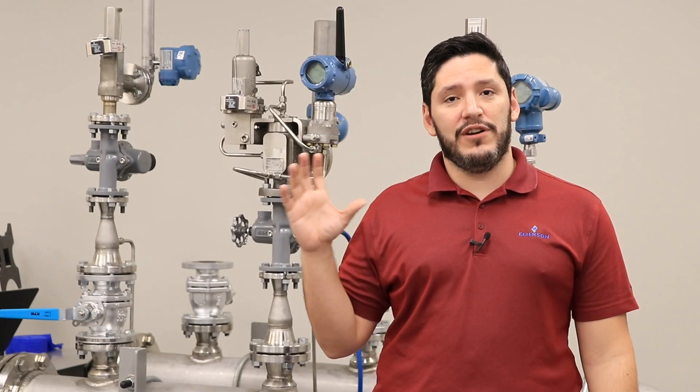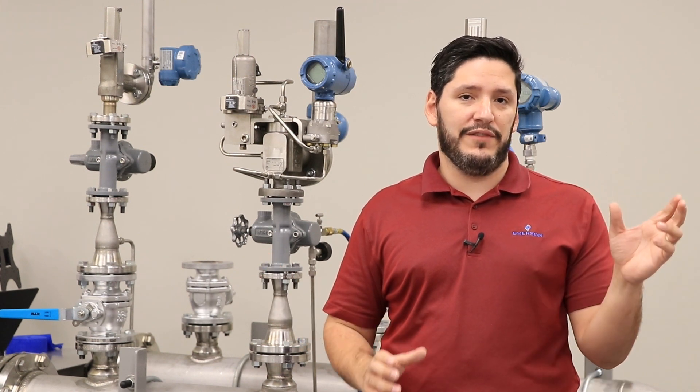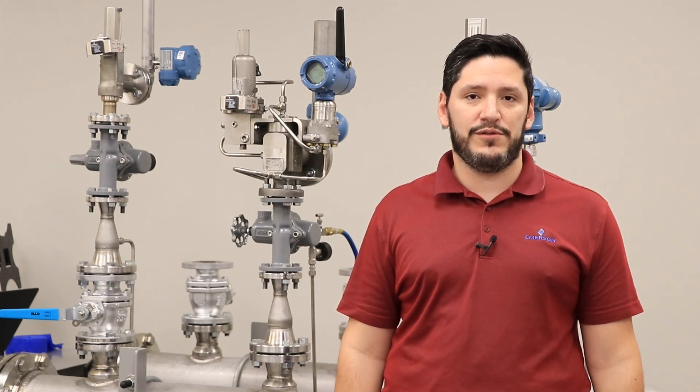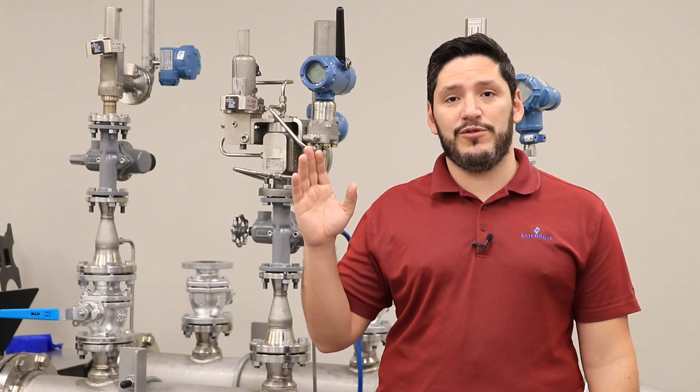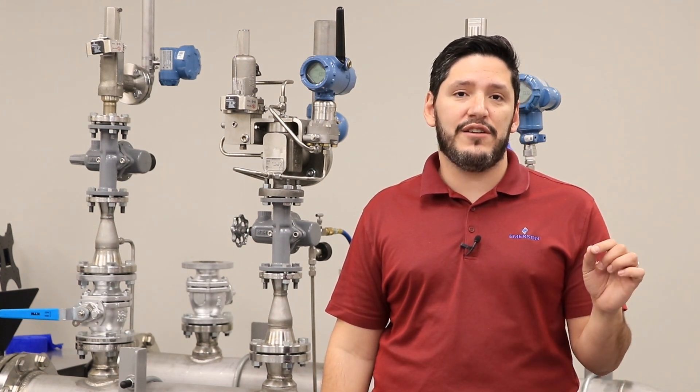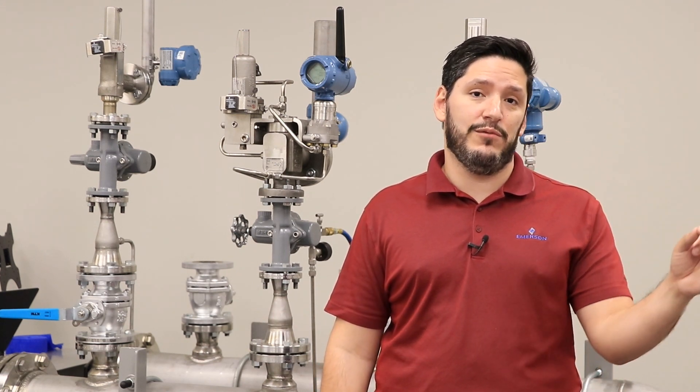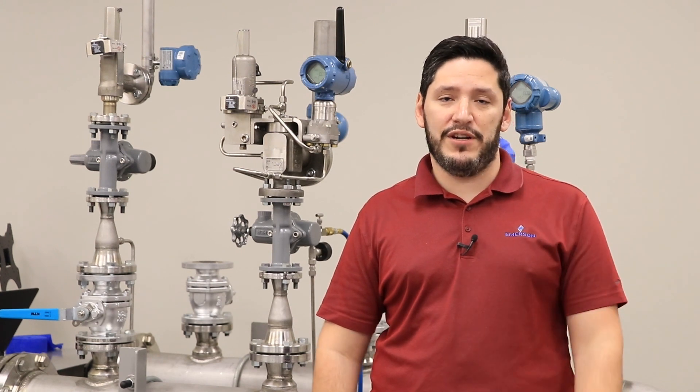We use a Rosemount 3051 or a Rosemount 2051 for our differential pressure transmitter and bellows leak detection solution. There are some benefits when we use the Rosemount 3051. The first one is accuracy. The accuracy on a Rosemount 3051 is 0.05% of the span calibration.